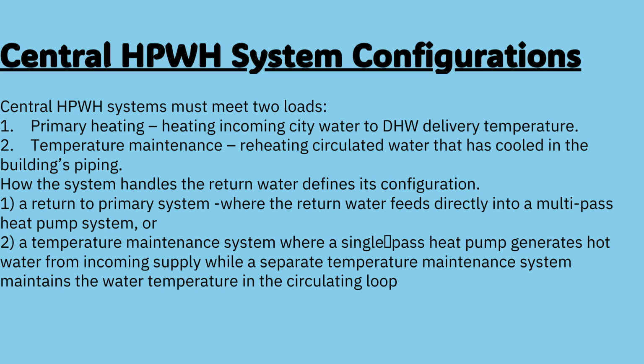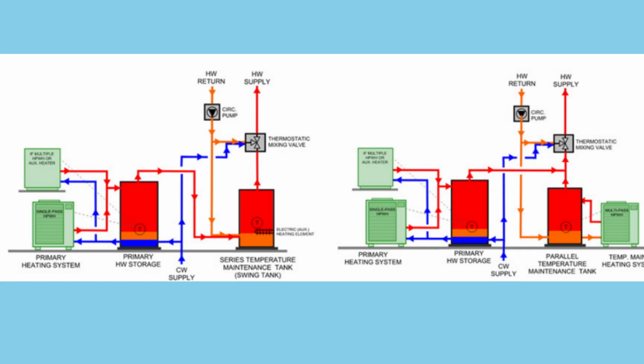1. A return to primary system, where the return water feeds directly into a multi-pass heat pump system. Or 2. A temperature maintenance system, where a single-pass heat pump generates hot water from incoming supply, while a separate temperature maintenance system maintains the water temperature in the circulating loop. Dedicated temperature maintenance systems are most common with single-pass heat pump water heaters, since they work best when heating cold water. To avoid mixing warm return water into the primary tank, we use separate equipment: a dedicated tank and sometimes a dedicated heater. There are two main designs.